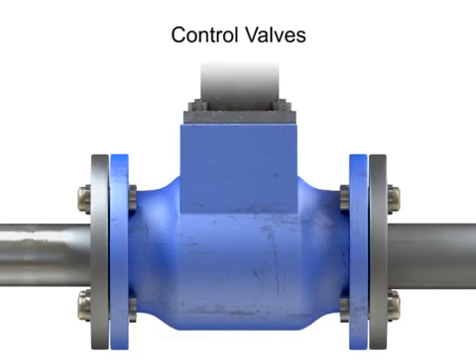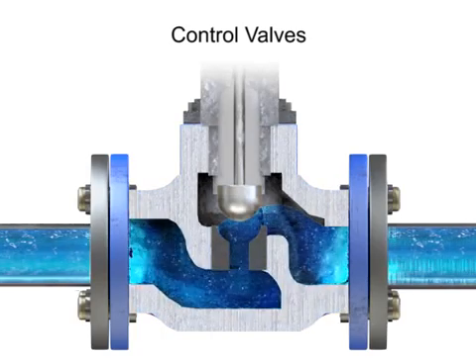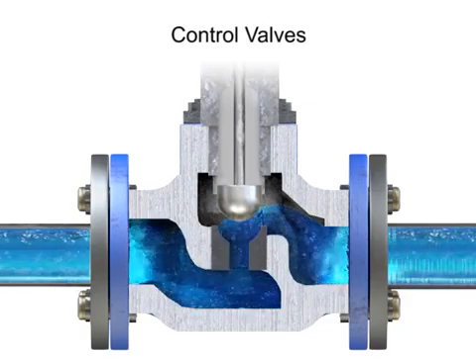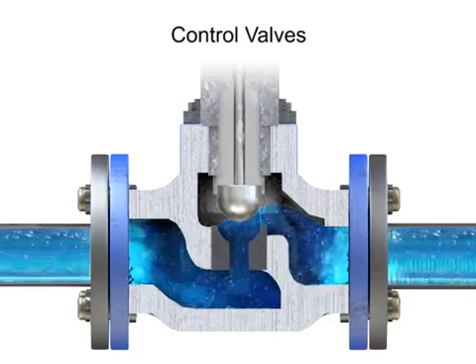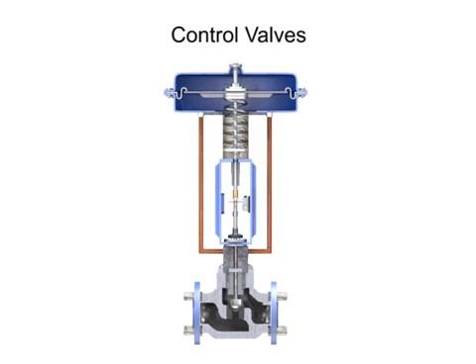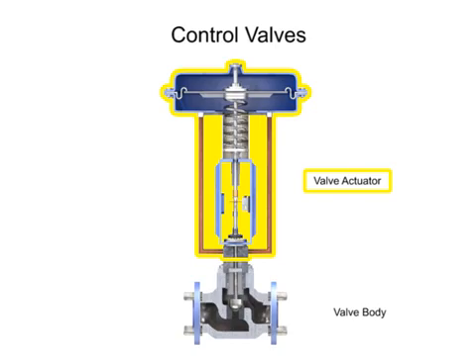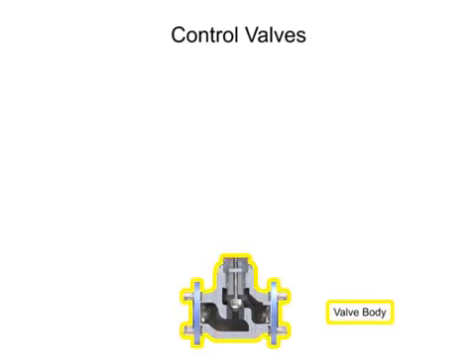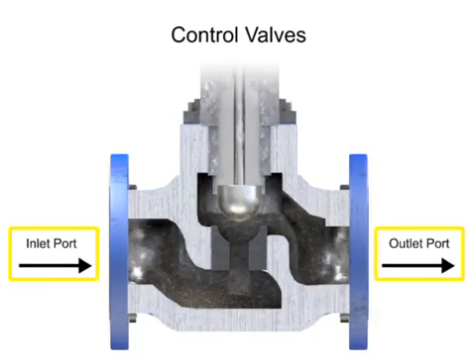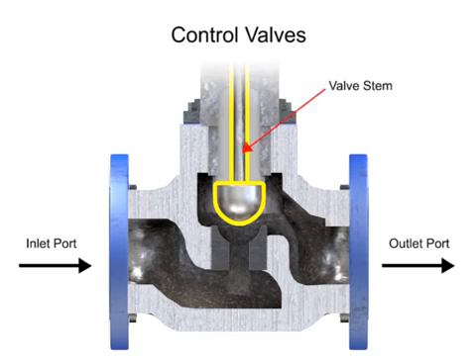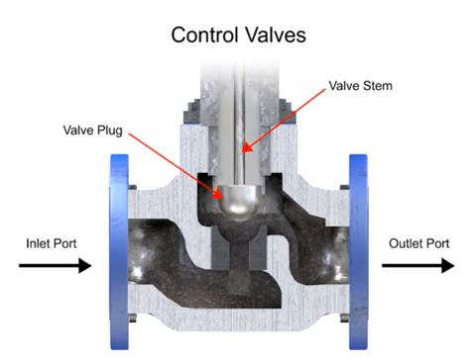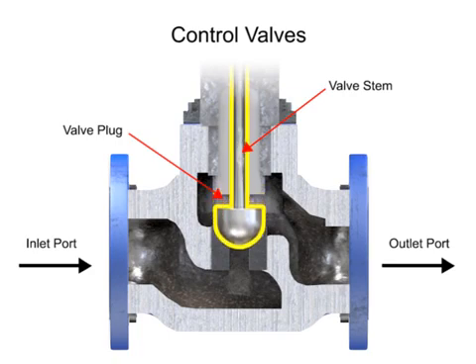Control valve actuators control fluid in a pipe by varying the orifice size through which the fluid flows. Control valves contain two major components: the valve body and the valve actuator. The valve body provides the fluid connections and a movable restrictor, comprised of a valve stem and plug that is in contact with the fluid and varies the flow. The valve actuator is the component that physically moves the restrictor to vary the fluid flow.